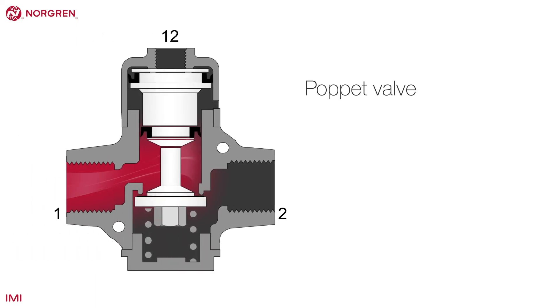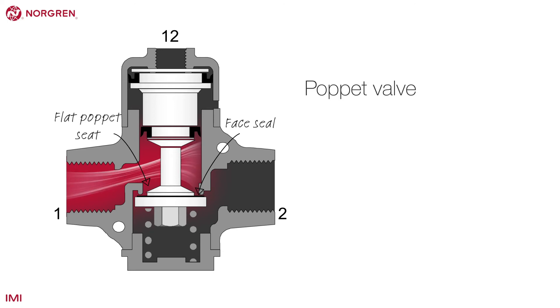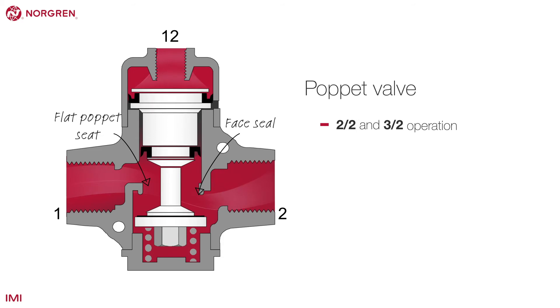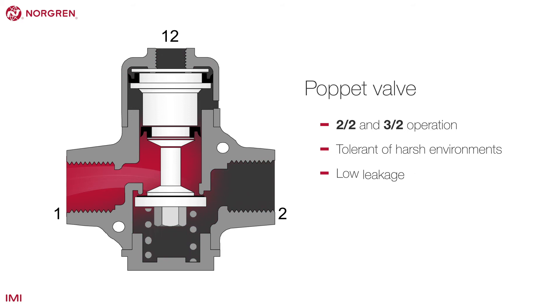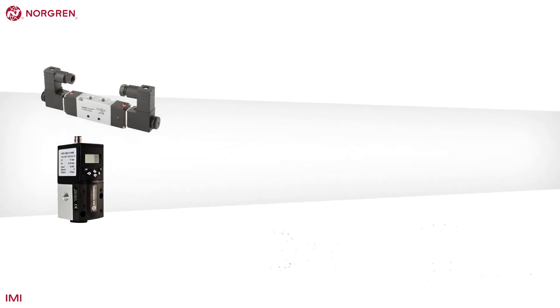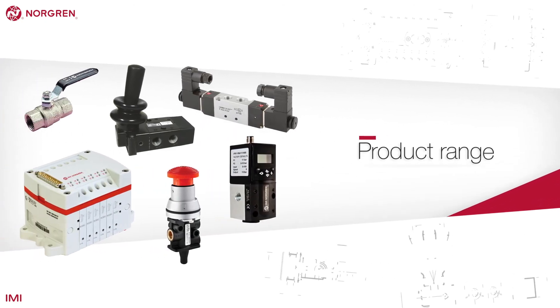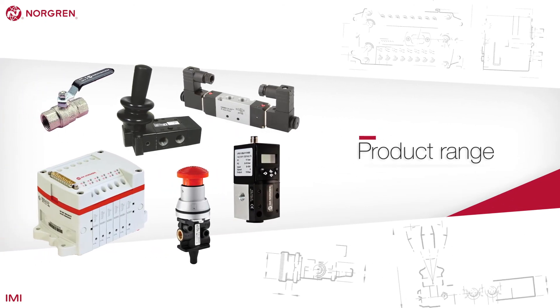A poppet valve is less common than a spool valve and operates in a different way, with a face seal acting against a flat poppet seat. These valves come in 2-2 and 3-2 operation, but are very tolerant of harsh environments, have a low leakage rate and can have a long life due to a lack of sliding friction. Now we have learnt about the theory, let's take a look at some of the control valves in the product range.